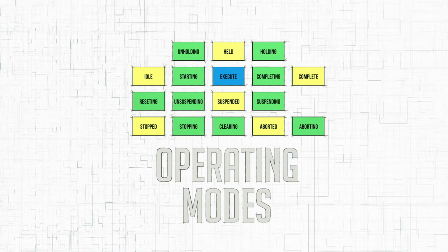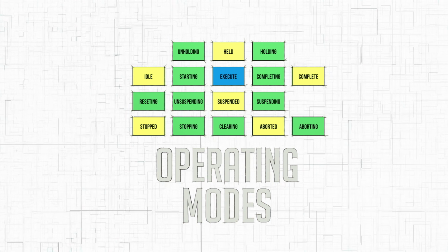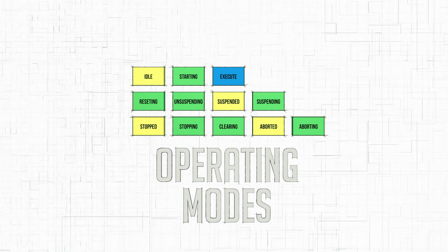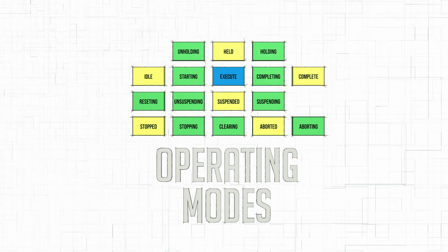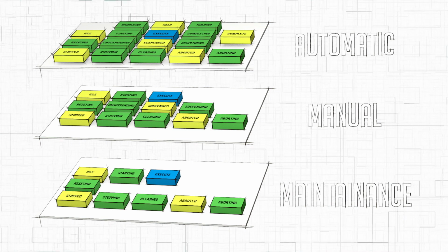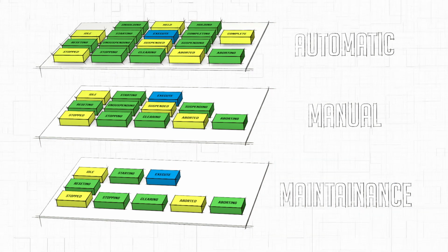PackML operating modes simply define what states are active in a particular situation. There may be any number of modes. They are user-definable by the programmer implementing PackML. Typically, they always include some form of production or automatic, manual, and maintenance.